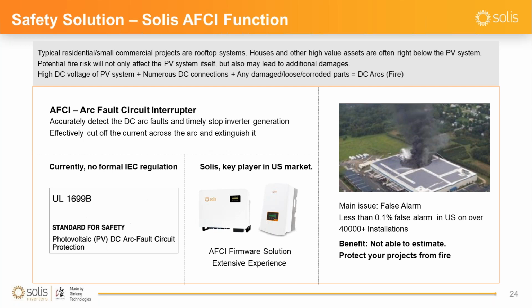And then any damaged or loose connector will cause a DC arc in the line, and if you do not cut off that current in time, it may lead to a fire disaster. So AFCI stands for arc fault circuit interrupter, and this function can accurately detect a DC arc fault in the DC cable, in a DC system, and then timely stop the inverter's generation. Once the inverter stops generation, they will cut off the current. There will be no current flowing through the DC cable, and that cuts off the current across the arc. So in that way we can extinguish the arc and protect your system from the potential fire disaster.